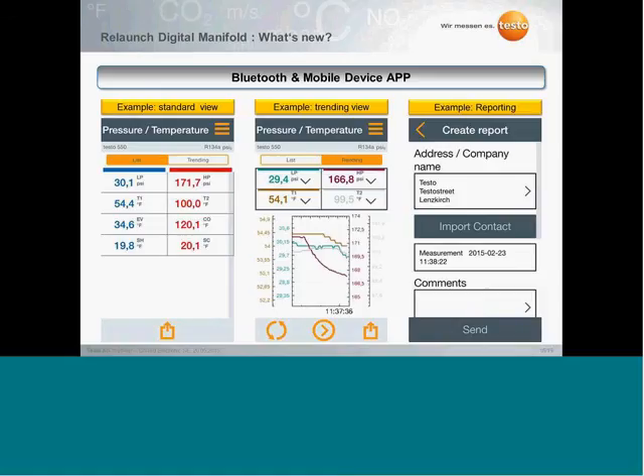Just to give you a brief overview, we have some of the screens here. On the left side, you see the standard pressure and temperature screen, where you see all your measured data in digits. Of course, you can also change here from PSI to bar, or from degrees Celsius to degrees Fahrenheit if you need it. In the middle, you see the trending view. You can choose up to 4 different values and trend them, and check how your values develop over time when you're checking or working on your system. On the right side, you see the report where you can put in an address, add pictures to the report, and also your measured data, and send this to your inbox for documentation, or for example to a customer.